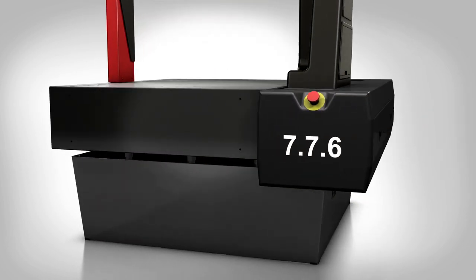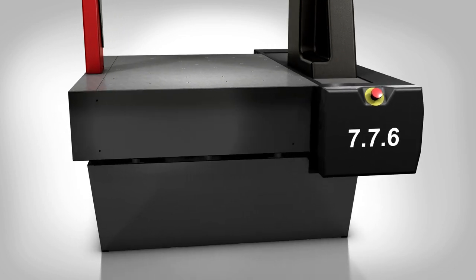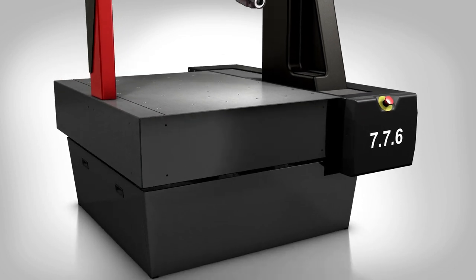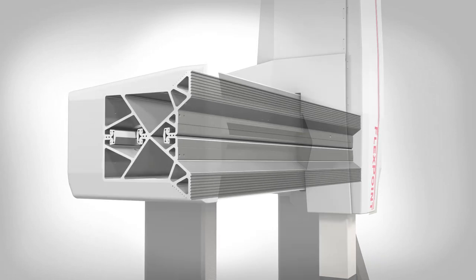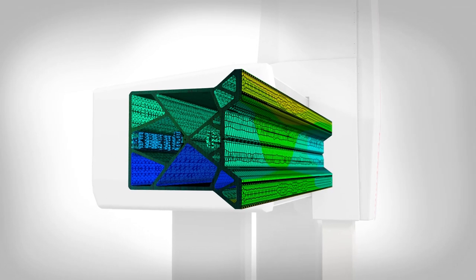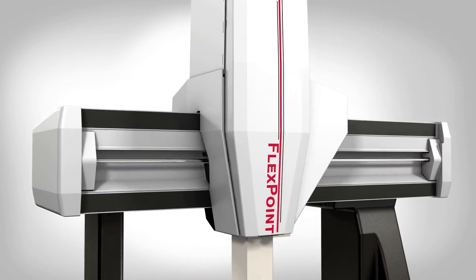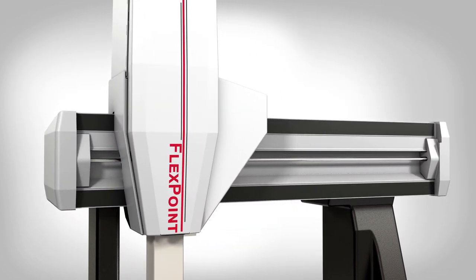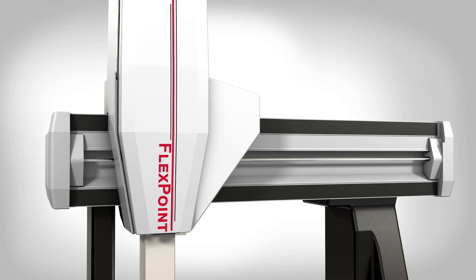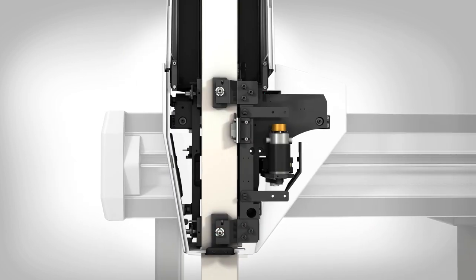FlexPoint systems are built on a single-piece granite surface plate with heavy cast uprights. An extruded aluminum crossbeam with a strong internal lattice forms a light but ultra-stiff bridge, supporting the z-axis and sensors, allowing fast motion speeds while ensuring ultra-low deflection.